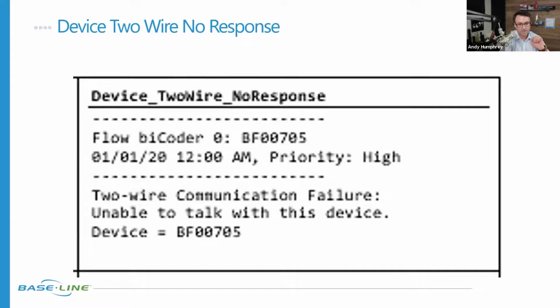We can send the signal out there, and in those instances, oftentimes the valves still work. The sprinklers still come on because the device is receiving the command, but it's weak enough where it can't make it all the way back. So it could be out of spec, or there could be one or a series of poor splices where we've lost that communication. Right. Nice.